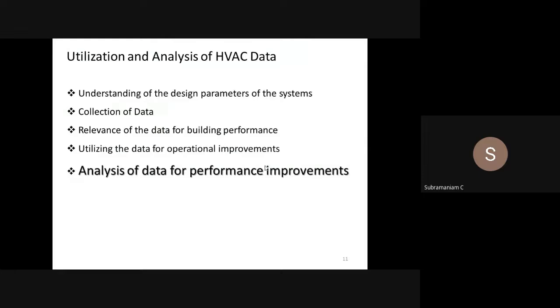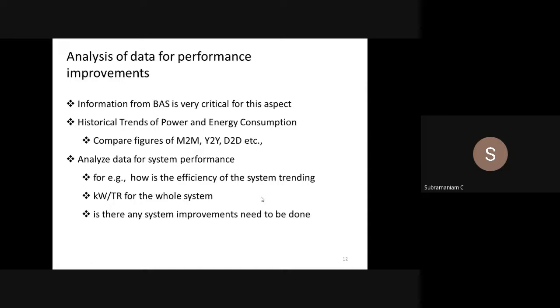So utilization of analysis of data is important for performance improvement. That is where we are talking about performance improvement of the machine. With analysis of data, we can always compare figures month to month, year to year. This day, last month, how much was it? This day, last year, how much was it? Am I consuming more power, less power? For example, my kilowatt per ton for the whole system, is it less? Is it more? What is my kilowatt per ton? When should I change my chiller, which is 10 years old or 12, 15 years old, right? So all that information is possible.